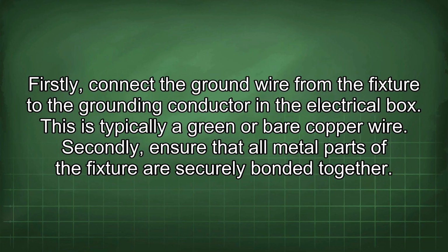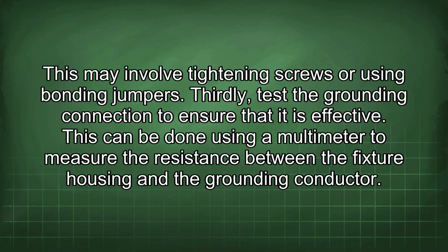Firstly, connect the ground wire from the fixture to the grounding conductor in the electrical box. This is typically a green or bare copper wire. Secondly, ensure that all metal parts of the fixture are securely bonded together. This may involve tightening screws or using bonding jumpers.